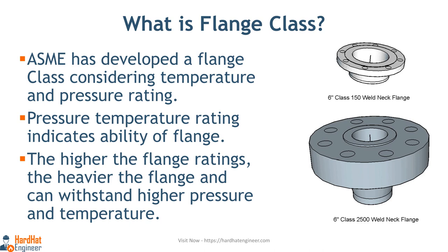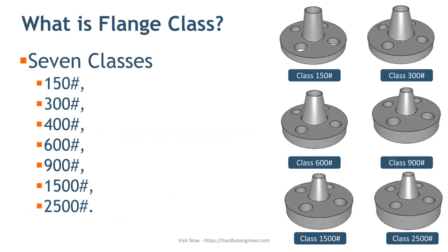As you can see in the image, there are 6-inch class 150 and class 2500 flanges. There are 7 flange classes: 150, 300, 400, 600, 900, 1500, and 2500. Out of these 7, class 400 is rarely used in process piping. As shown here, as the rating increases, the flange body thickness also increases.